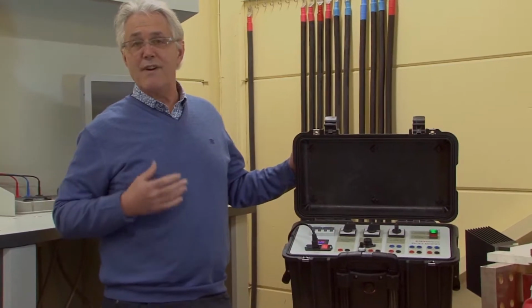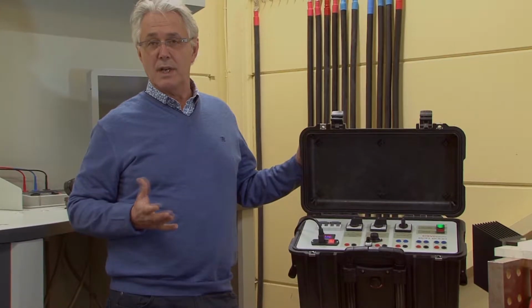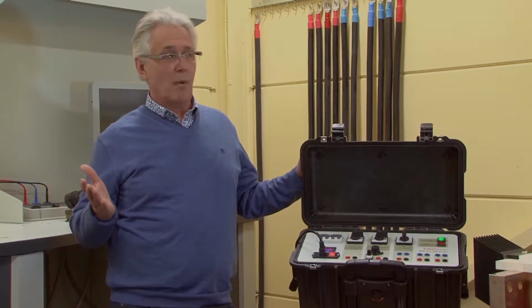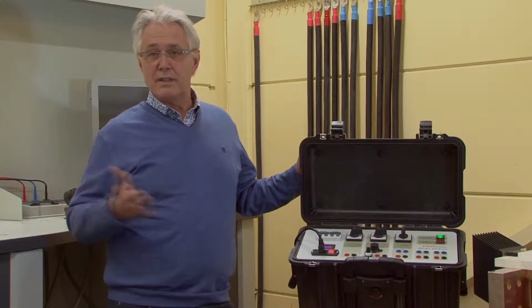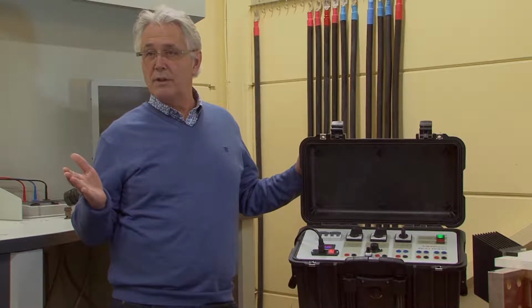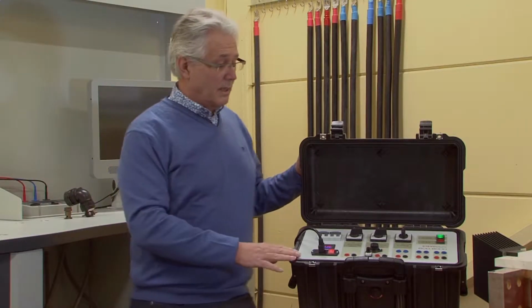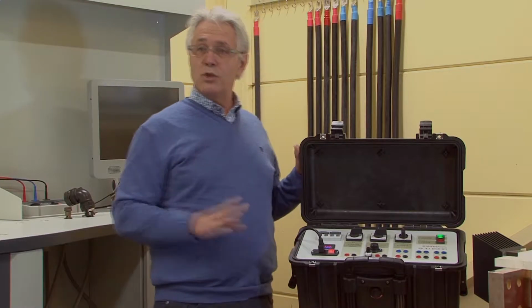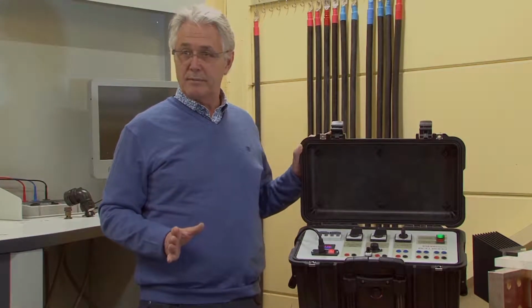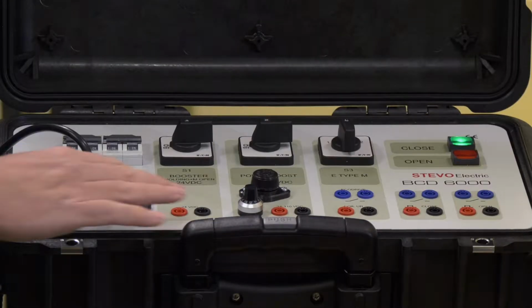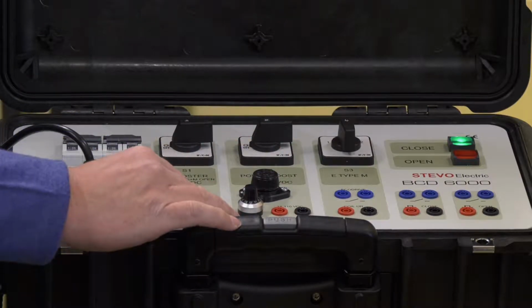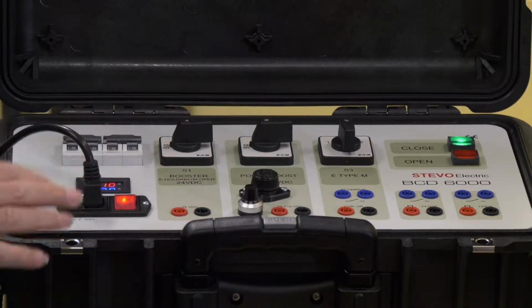110 volts is very often used for circuit breakers, but you have circuit breakers which operate at 48, at 60 volts, 72 volts, 90 volts. This is a very versatile unit, so it should work with any type of breaker. So the two power supplies, 24 volts, 110 volts DC.